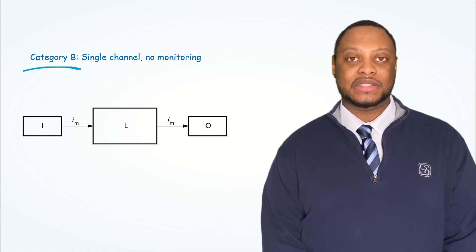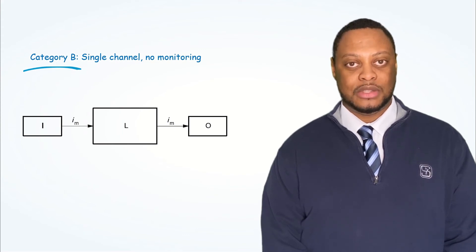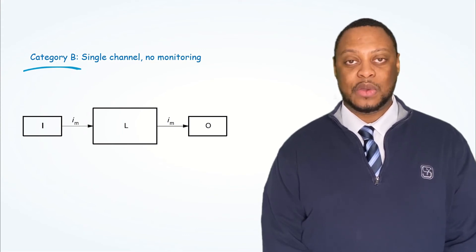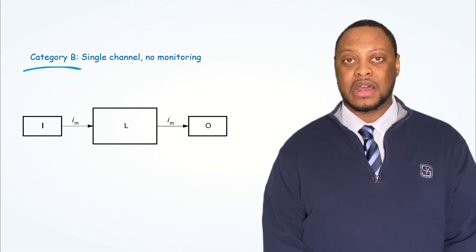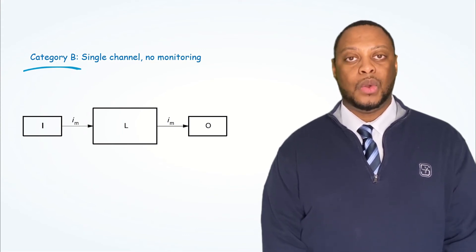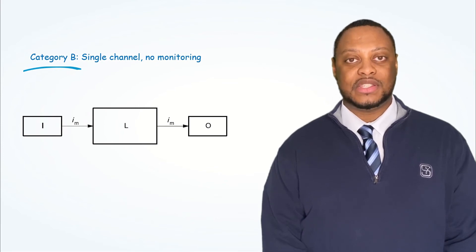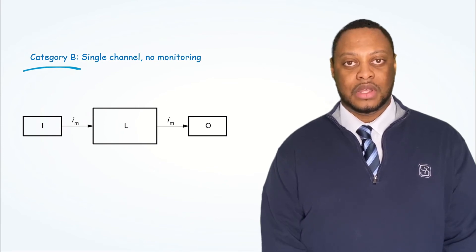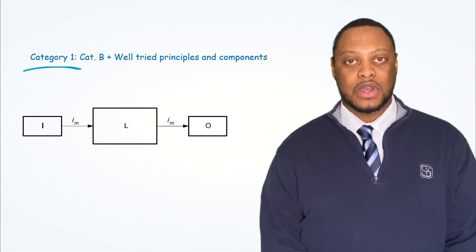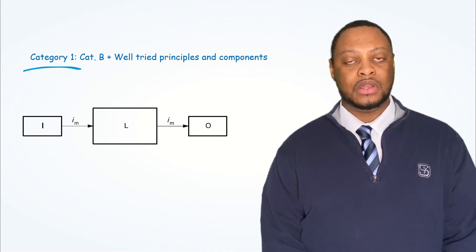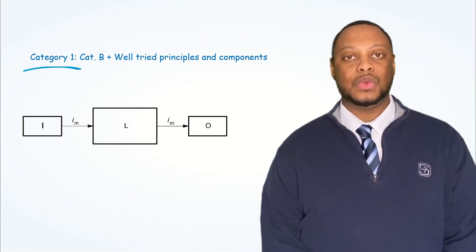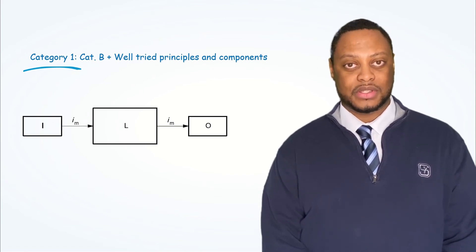Category B is the baseline for machine safety control systems — it is a single channel with no monitoring. One failure and you lose your safety function. Category 1 is the same idea: single channel, no monitoring, but we're using well-tried principles and components.